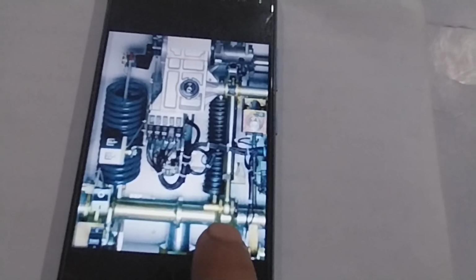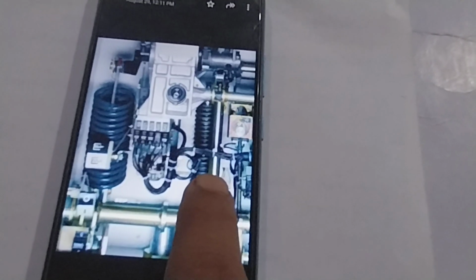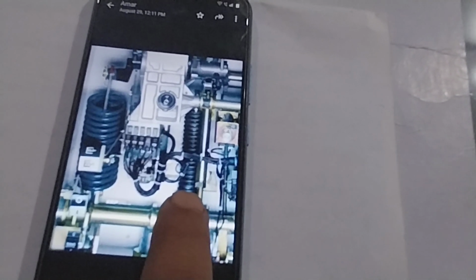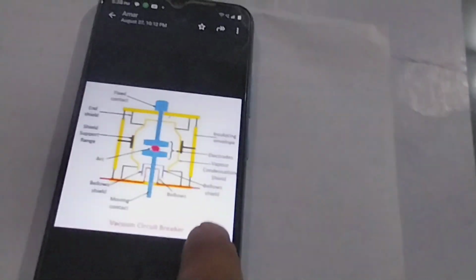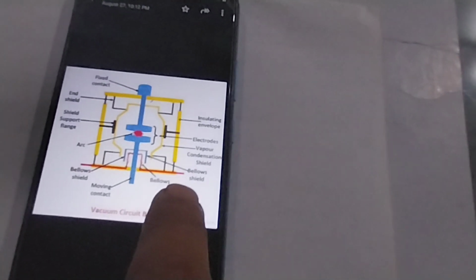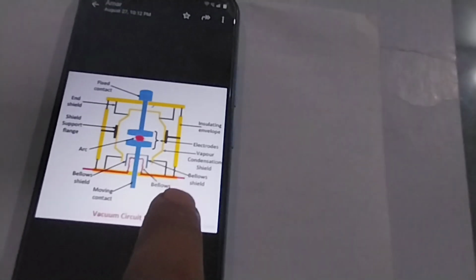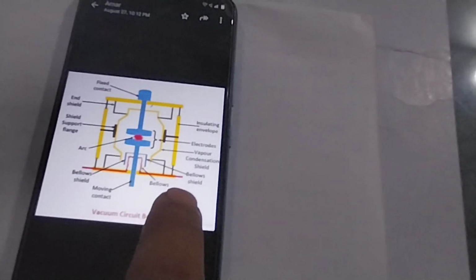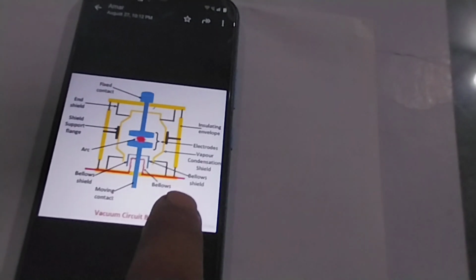Waiting until the circuit breaker is fully closed before starting the opening operation is not a preferred option. Most types of circuit breakers, therefore almost all types of high voltage circuit breakers, have a mechanism whereby the tripping action is initiated any time after the start of the closing operation, preferably before closing of the circuit.